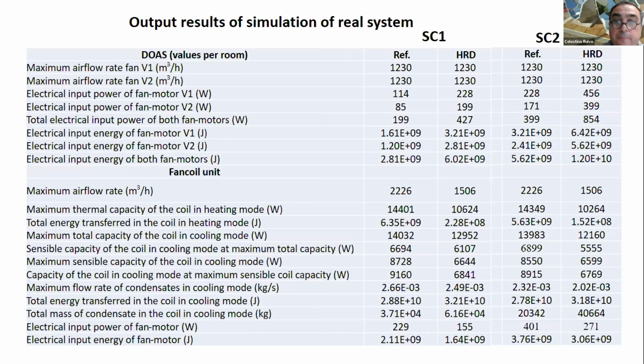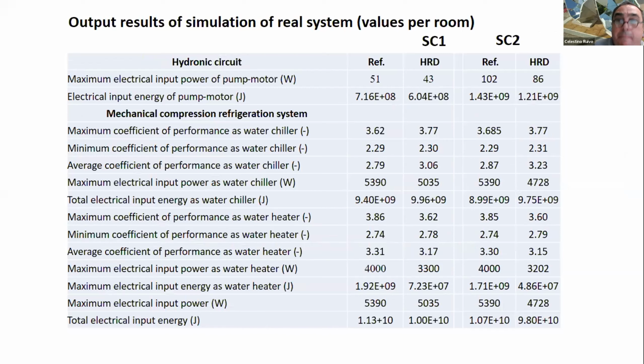Regarding the fan coil, the impact of using a heat recovery device in the dedicated outdoor air system leads to a non-negligible reduction in peak thermal capacity and also in power and energy consumption of the respective fan motor of the fan coil. The same impact is verified in the case of the pump of the hydronic circuit.